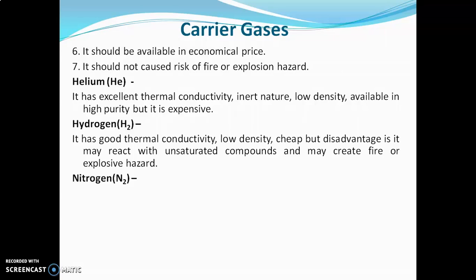Hydrogen is also having a good thermal conductivity, low density. It is cheap also. But the disadvantage is that it may react with unsaturated compounds and may create fire or explosive hazard. Next is nitrogen. Nitrogen is inexpensive but it gives reduced sensitivity of detector. Amongst these, we have to select one of the carrier gas depending on our requirement.